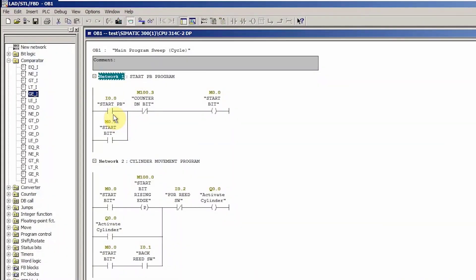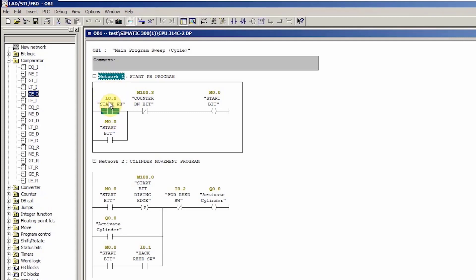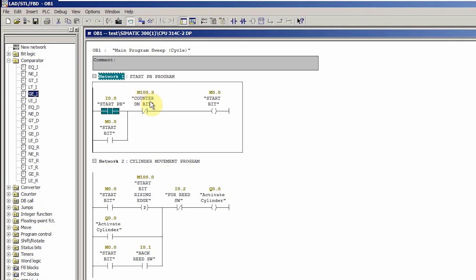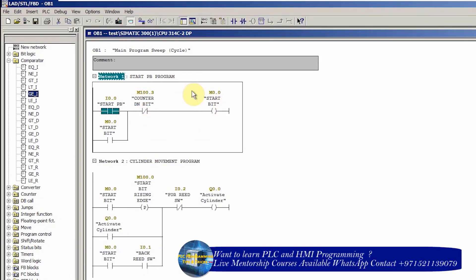In the first rung we write the program for the start push button. The start push button at I0.0 turns on the start bit M0.0. This start bit is latched on through a normally open contact M0.0 — since the contact has the same address as the output coil, it holds M0.0 on. The start bit can only be unlatched when the counter done bit M100.3 turns on, because a normally closed contact of M100.3 is used here.